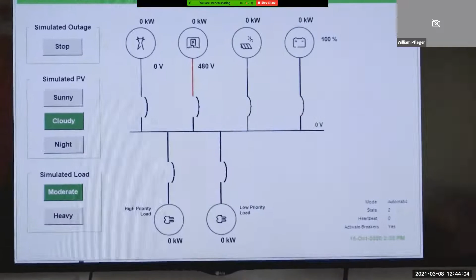Generator comes on, give it a couple seconds, close in the various breakers, and now we've got everything re-energized except the utility, which is at 0 volts, that we've separated from. Again, this is a great situation when the sun is shining, but if it's nighttime, now the generator's really working hard at 370 kilowatts.